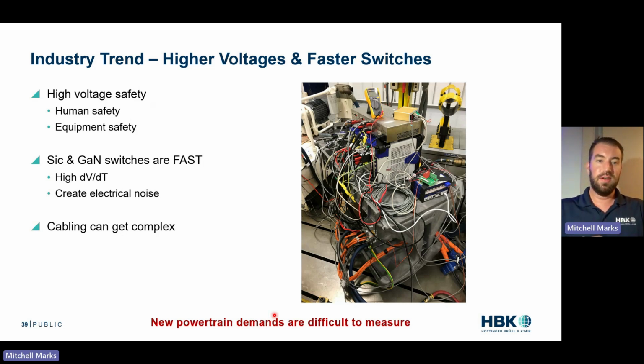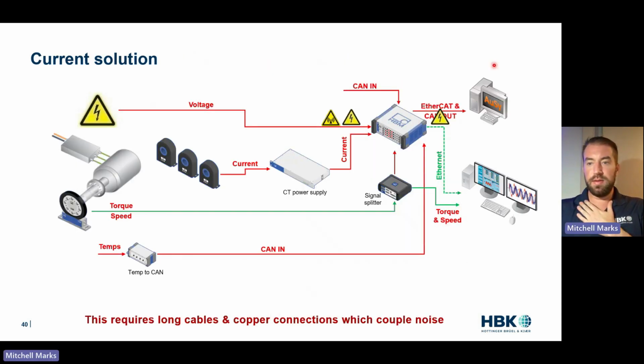And a typical test setup ends up looking something like this, where we have copper cable coming into an instrument, current sensors, copper cable to a power supply, copper cable to the instrument, torque and speed coming over copper, and then things like temperatures coming over CAN bus. This requires long cables, copper connections, which couple noise. You can put the instrument close to the measurement unit, but is that always practical?